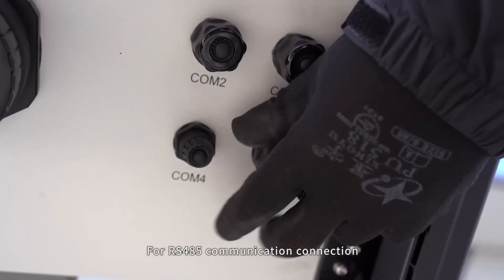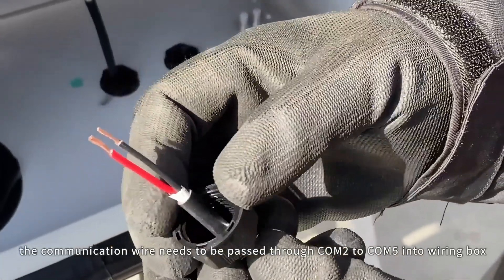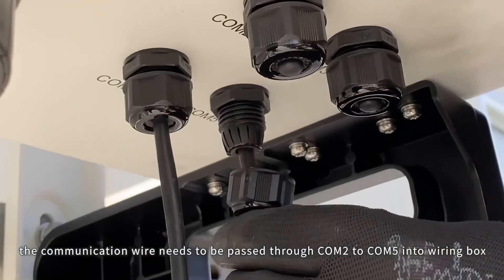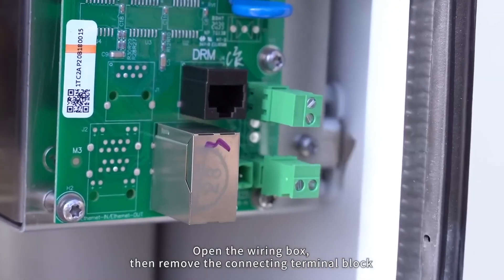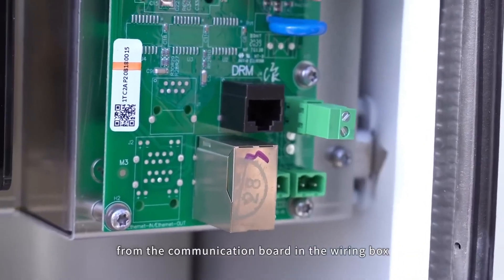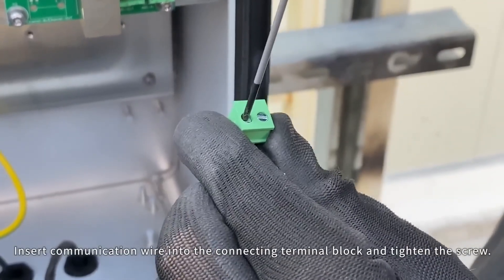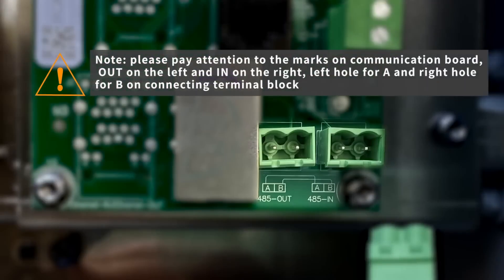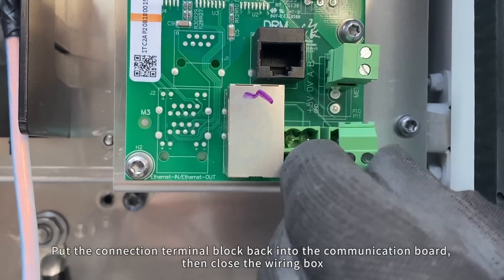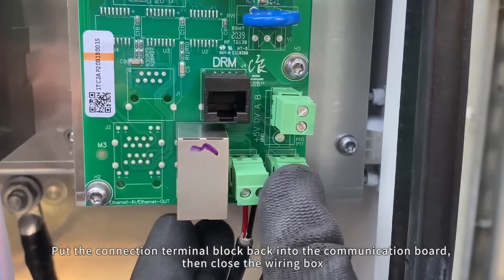For RS-485 communication connection, the communication wire needs to be passed through COM2 to COM5 into the wiring box. Open the wiring box, then remove the connecting terminal block from the communication board. Insert the communication wire into the connecting terminal block and tighten the screw. Put the connection terminal block back into the communication board, then close the wiring box.